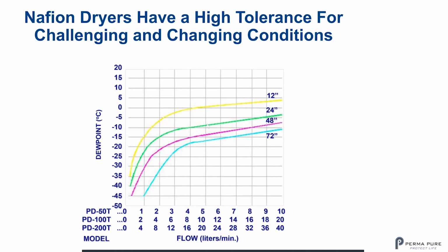If you double your flow rate from 5 to 10 liters a minute, your dew point goes from -8 to -4. So what you're seeing is that you could double the flow rate. That means doubling the moisture being put through the dryer. You could see that the dryers have a high tolerance for changing conditions. That means the dryers aren't going to spit out water and send water to the analyzer optical bench if any problems occur. It's very important to understand that.